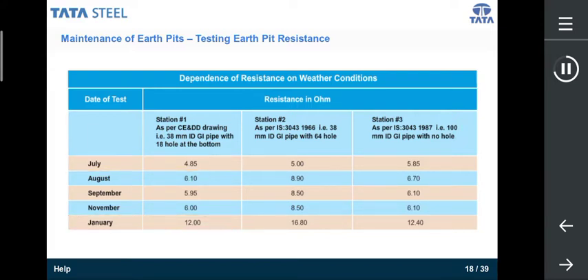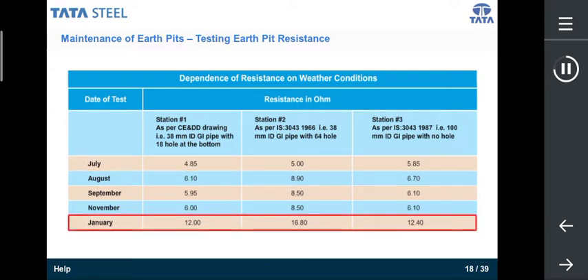Also, if you look at the last row, the values have been consistently high in the month of January across all the 3 stations. Therefore, maintenance of each earth pit should be done when the resistance values are high. Further, this maintenance should be done during the dry seasons only, that is between January to March.